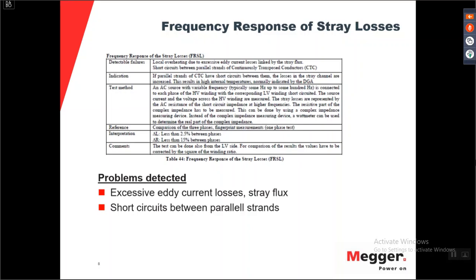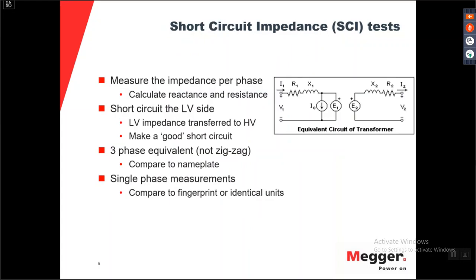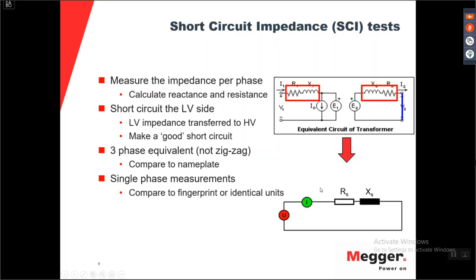And the reference for this is, of course, you compare the 3 phases. And then you look at the delta L and the delta R. It should be less than 2.5% and less than 15%. I will shortly explain what I mean with the delta L and the delta R. So if we look at the short circuit impedance test, you remember we're looking at the R and the L with the secondary side short circuited. That will give us the equivalent circuit of the voltage, the current, with a resistance and an inductance. So we will actually have only a resistive part and an inductive part.